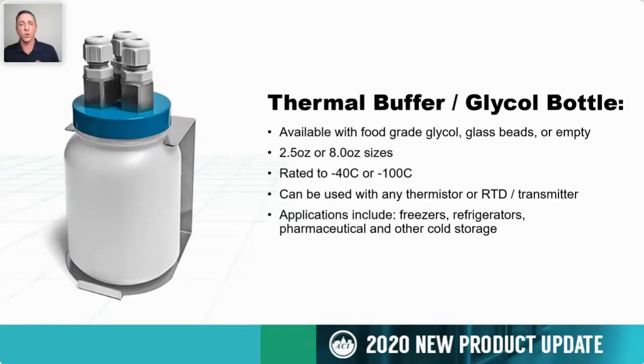The fifth new product addition that we'll discuss today is we've expanded the thermal buffer and glycol. That one comes with 3 ports in the top for applications where it requires multiple redundancies. So you can put up to 3 different sensors within that bottle. We can ship them either empty, just the bottle by itself, or filled with a food grade glycol solution that's rated to -40 C. Or a new option, we can ship them filled with small glass beads that are rated to -100 C.